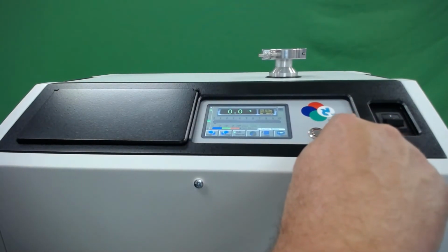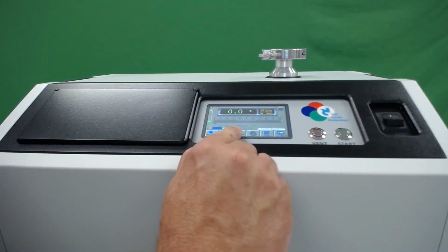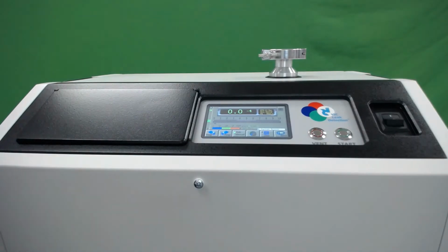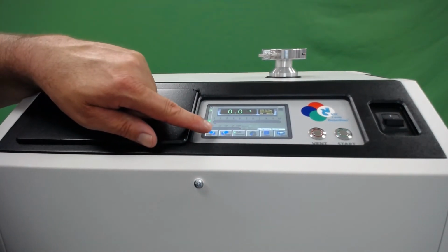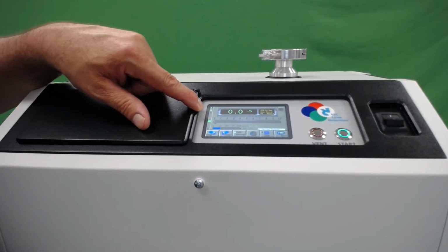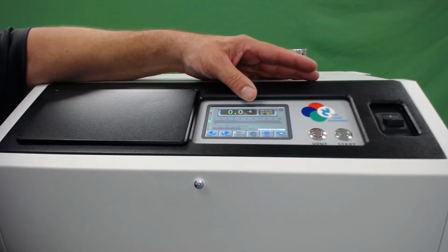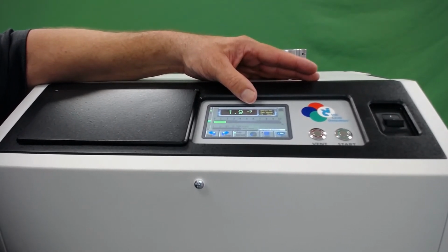To initiate a cycle, you press start. The test port will begin evacuating. Once it reduces to a low enough pressure, the machine will begin reverse testing, which is indicated by the letter R. And because it's in automatic ranging mode, the machine will select the best resolution to display what the current leak rate is.